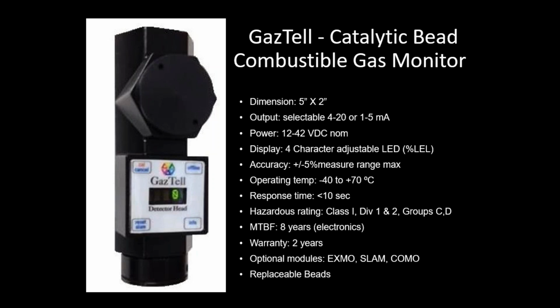Again, the beauty of this is all the GazTell sensors all use the same body. It's the 5x2 body. It's the same 4 to 20 output. It's the same power requirements. So everything is identical. What changes is really the sensor, and in some cases the front end electronics to operate the detector, the sensor element itself. MTBF is always the same. Warranty is typically the same, except for electrochemical. You'll see that the cells are warranted for 1 year rather than the life of the unit, which is 2 years. And that's just really a function of the electrochemical cell.